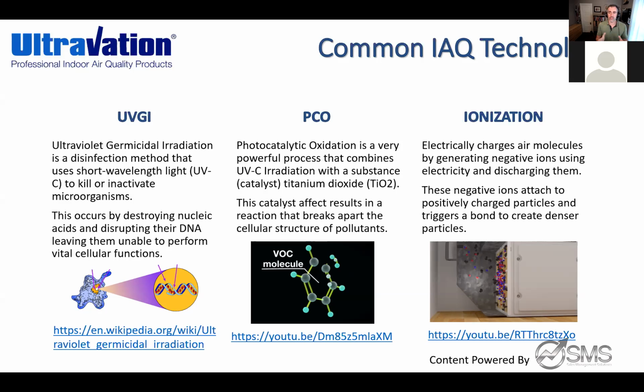Long story short, you cannot apply, as they call it, UVGI technology in an HVAC application unless you're using UVC class wavelength bulbs. A lot of people don't realize that, especially if you go on Amazon nowadays - there's UV products that don't even tell you what kind of UV it is, it just says UV lamp. Well, there's a difference. There's the UVA light spectrum, the UVB section of the spectrum, and UVC. With the recent updates from CDC as well as ASHRAE, they all agree: if you're talking about UV application, you better be using UVC wavelength bulbs.